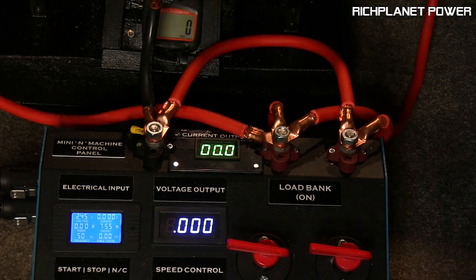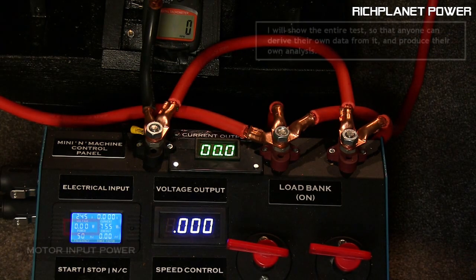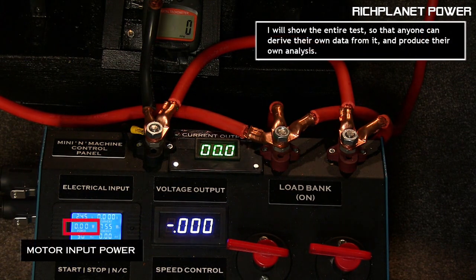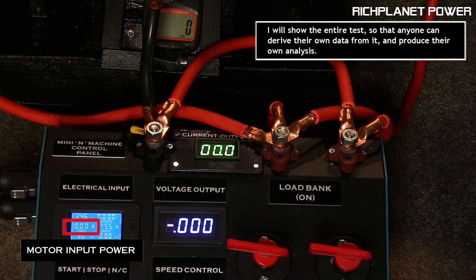Okay, so this is a video of the test run of the homopolar generator machine, and what it's going to consist of is running the machine up to speed, then switching the load on for 10 seconds, then switching it off for 10 seconds, on for 10 seconds, off for 10 seconds, 10 full cycles with all of the instruments recorded. I've got an audio signal in order to time the 10-second intervals. I think the output current should be in the region of 60 amps with the way that I've got the load configured. Alright, so let's start it up.